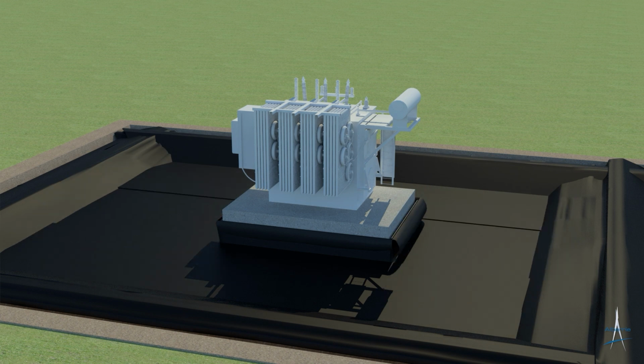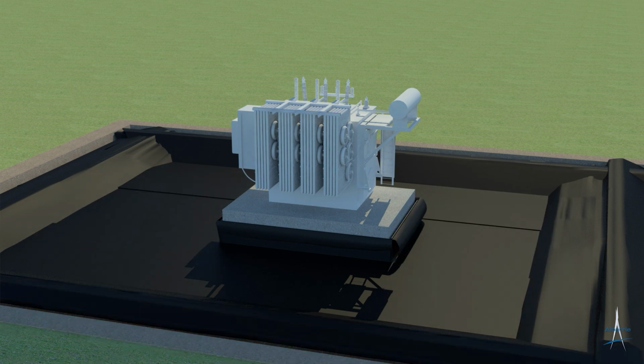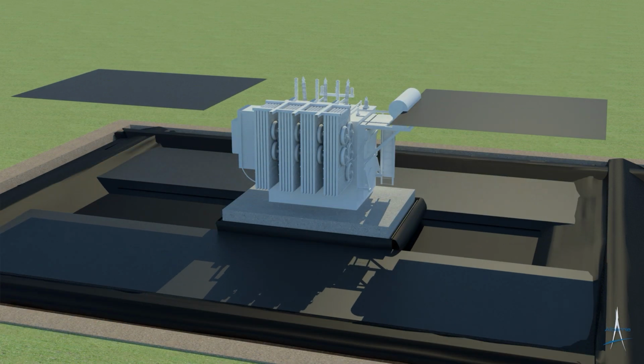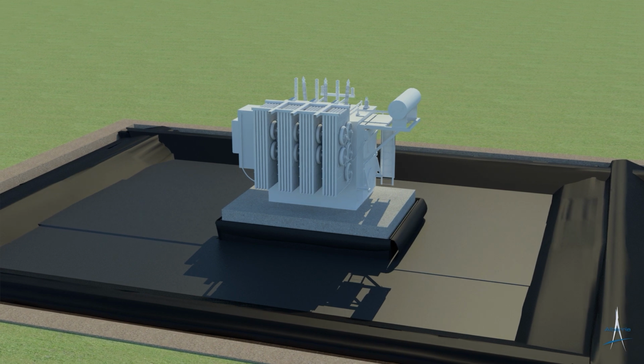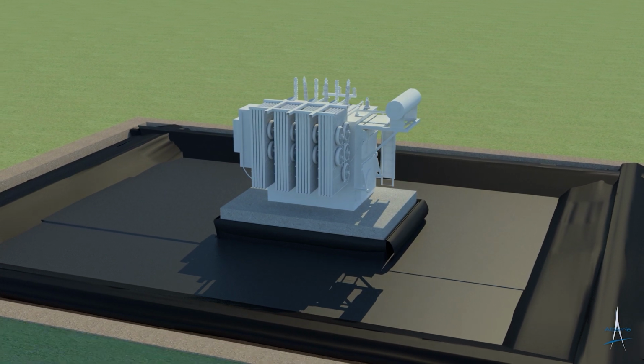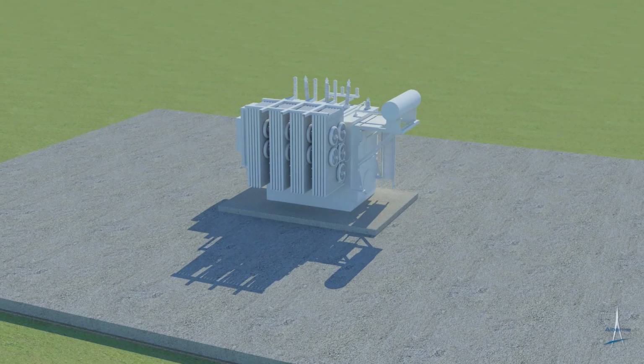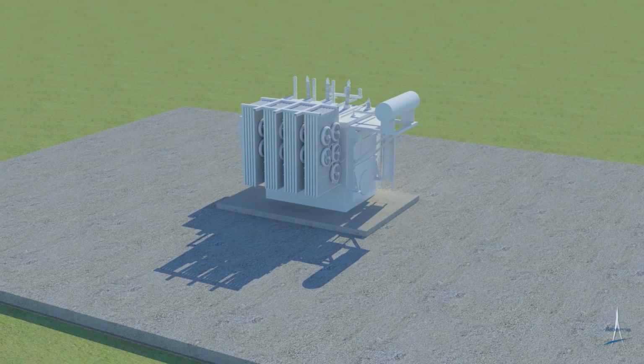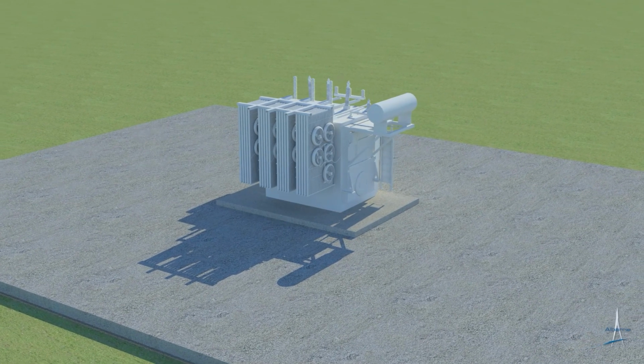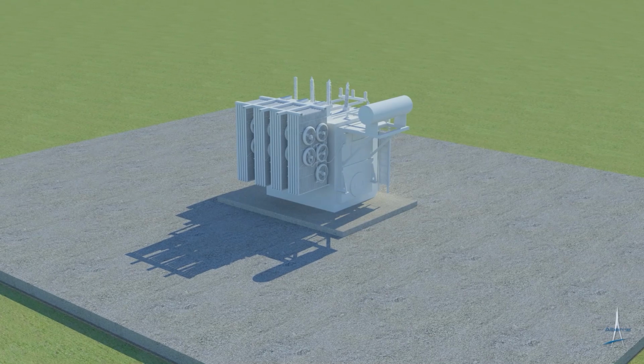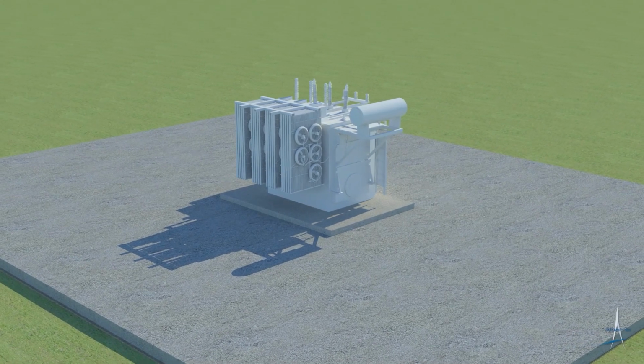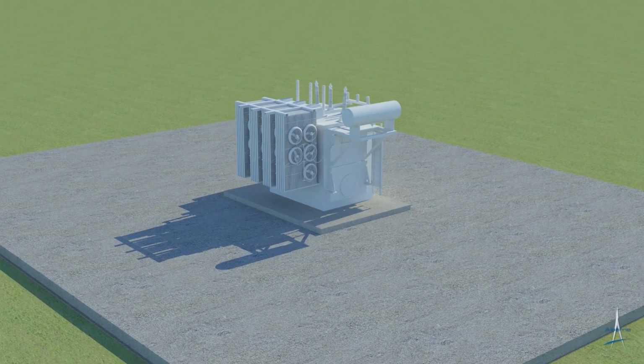Non-woven is laid out and will act as a separation layer, followed by the woven geotextile, which is used to move the liquid laterally throughout the containment. The system is filled with fire-quenching stone, which limits and prevents the spread of fire. Finally, the containment is topped and leveled off with substation cover stone to the designated design height.